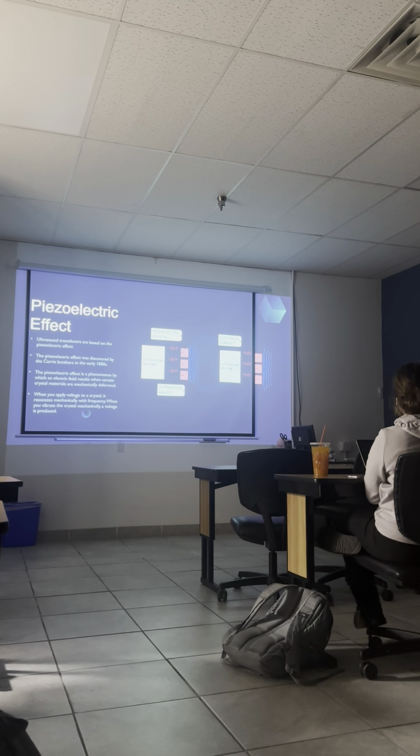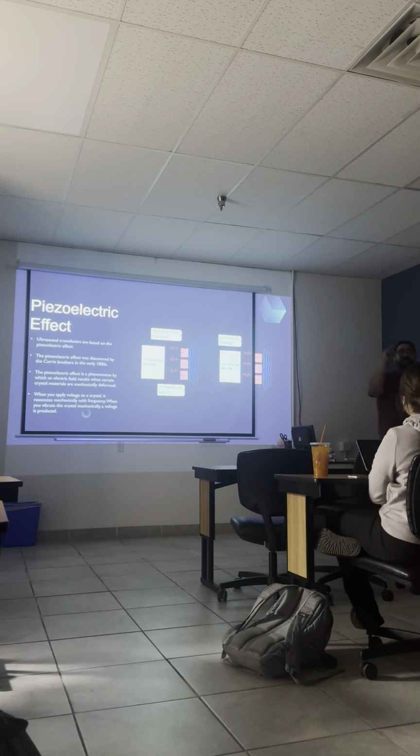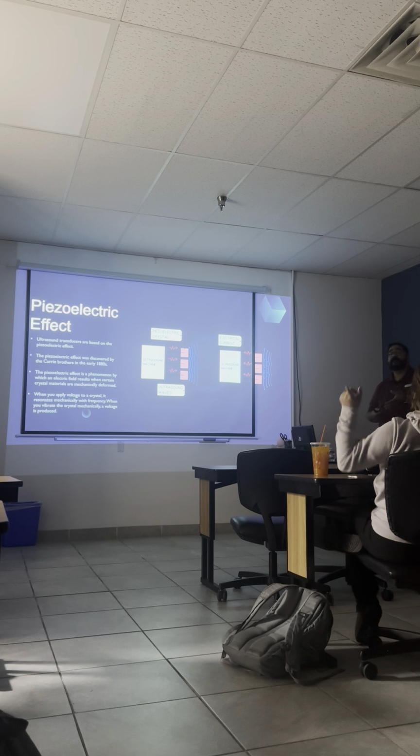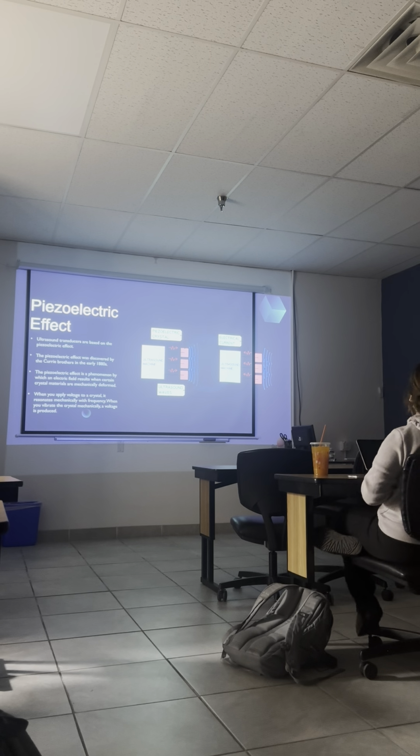But the crystals are already polarized, right? In a transducer, the PZTs and quartz. Let's say that we made a PZT crystal here, we would have to polarize it. But the ones in the lab, yes, all of the ones that are functioning as an ultrasound transducer have been polarized.